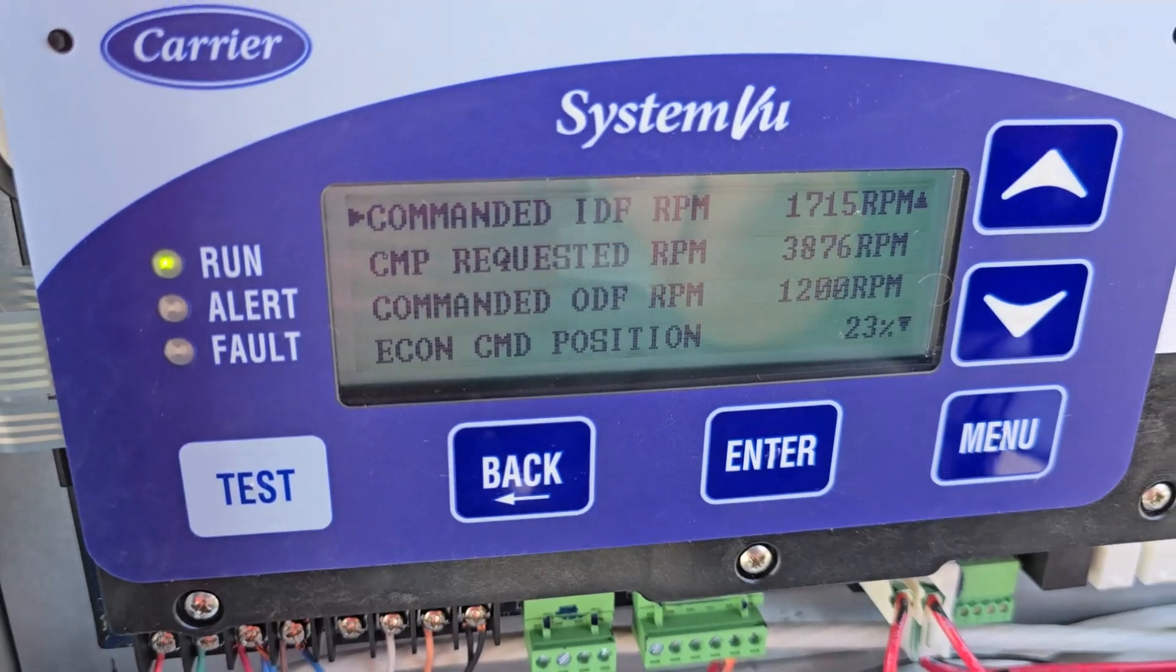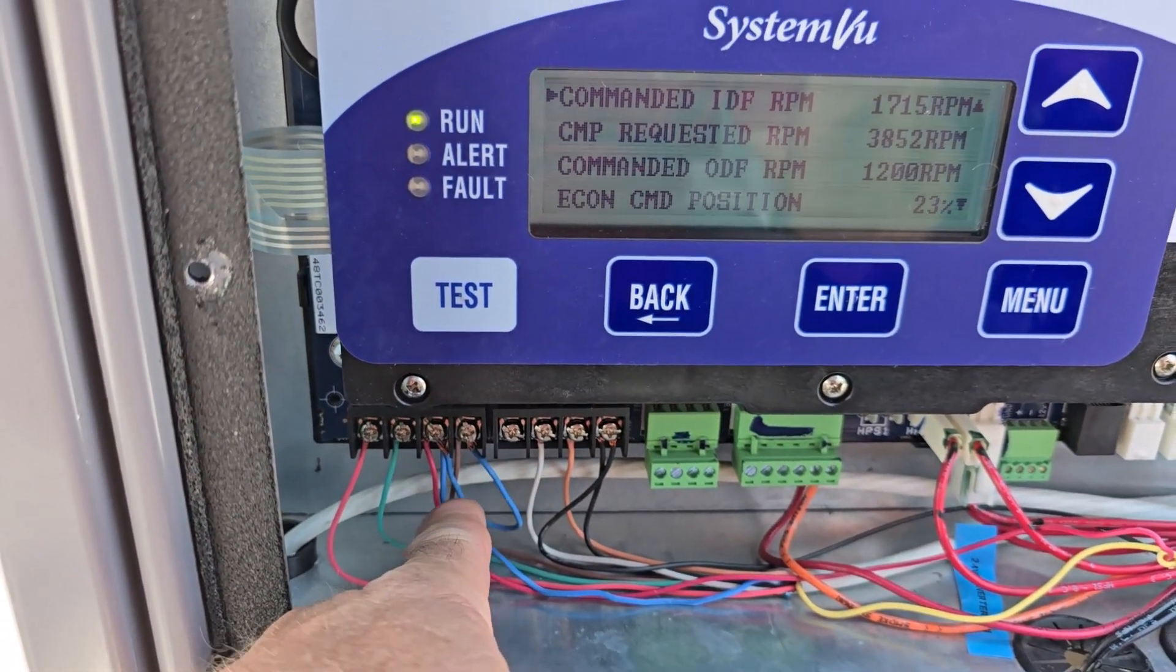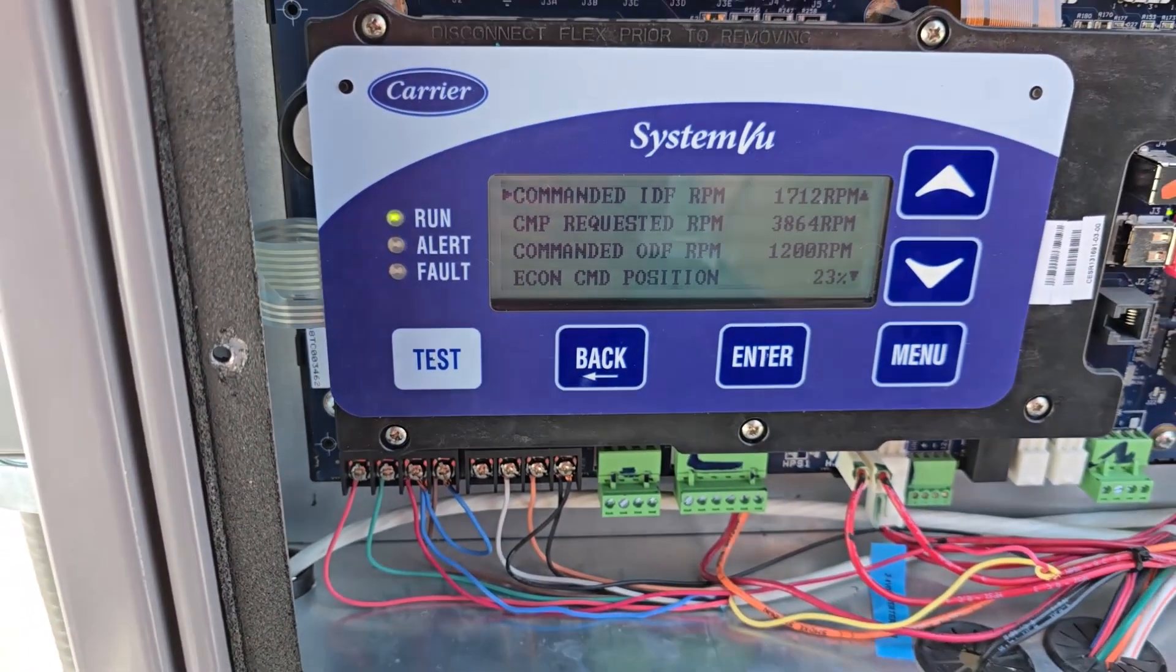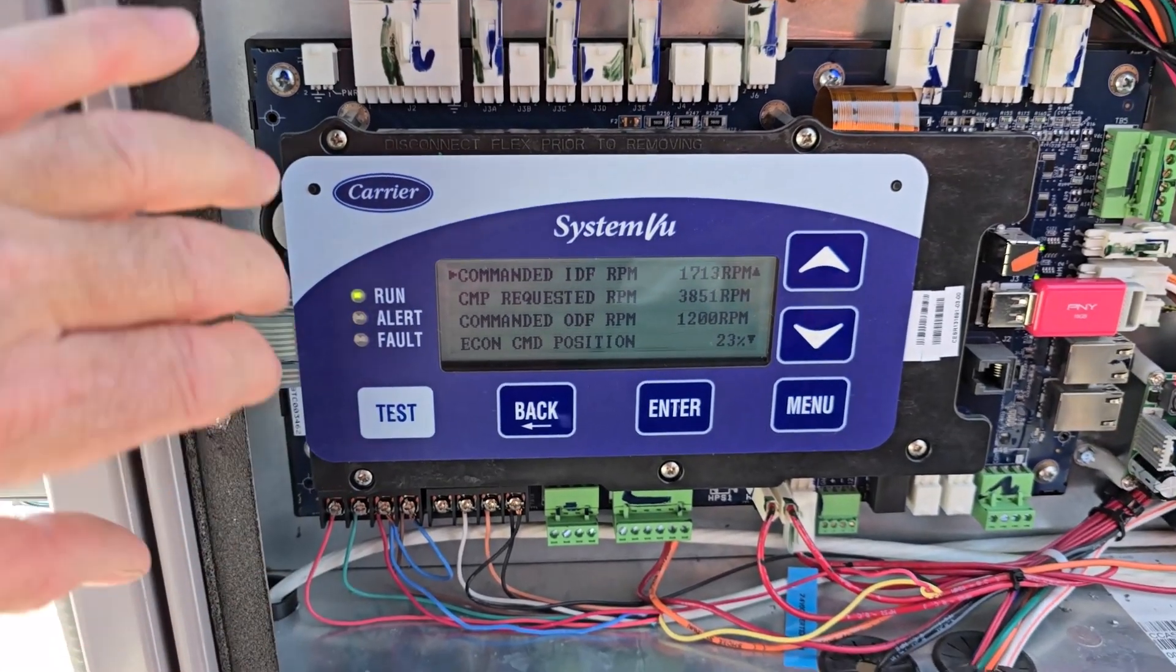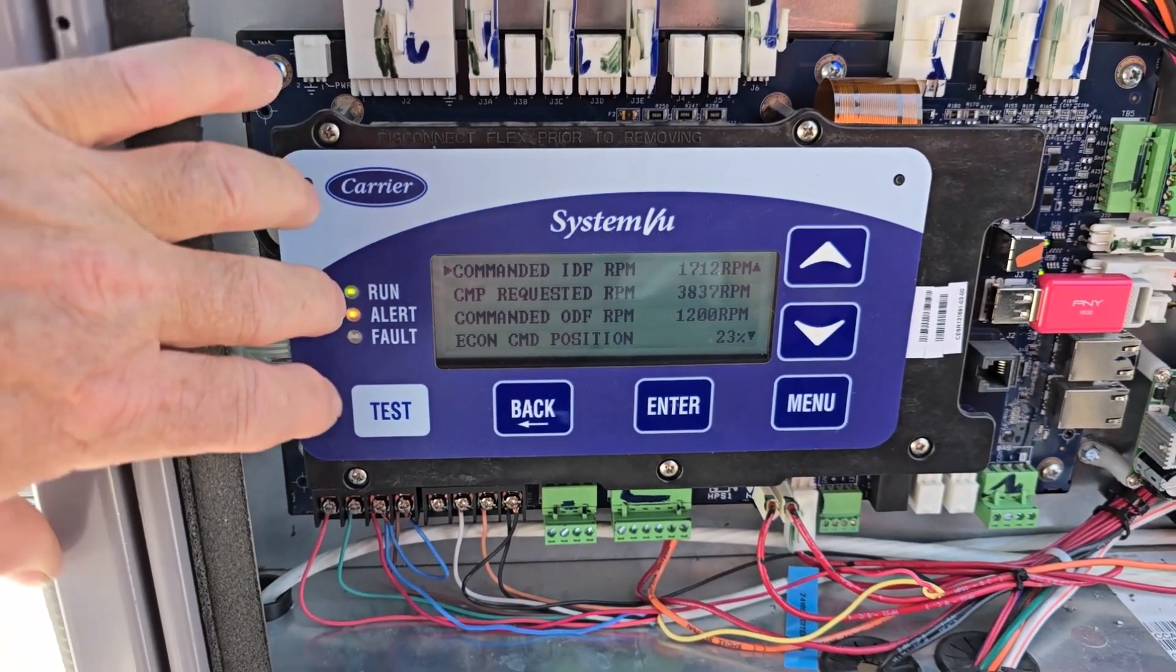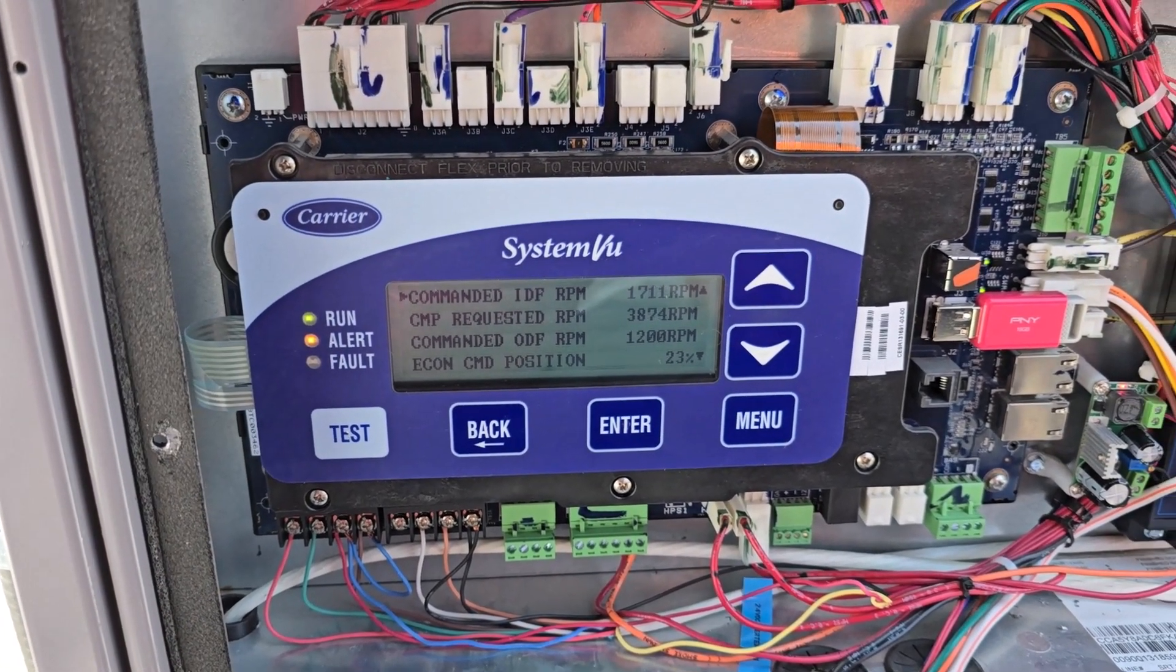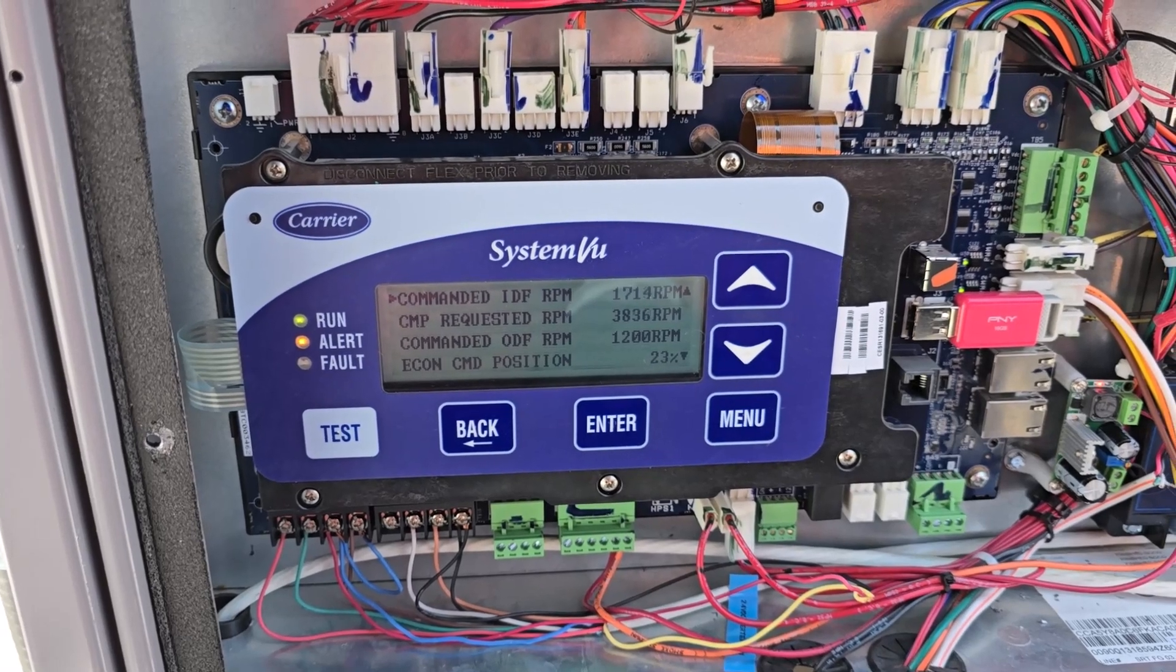That will auto reset. So I've been running this for a while off the thermostat. I had to add a jumper because Y1 is not working on that thermostat causing an alert for improper thermostat input. So I just run on Y1 and Y2 now.